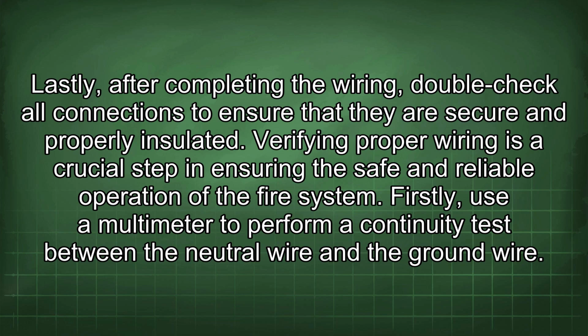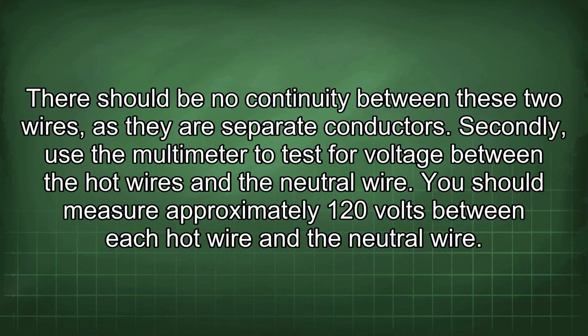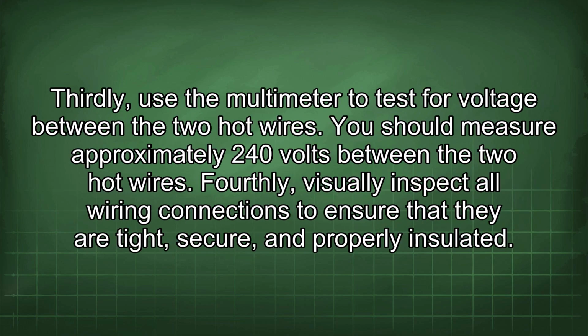Firstly, use a multimeter to perform a continuity test between the neutral wire and the ground wire. There should be no continuity between these two wires, as they are separate conductors. Secondly, use the multimeter to test for voltage between the hot wires and the neutral wire. You should measure approximately 120 volts between each hot wire and the neutral wire. Thirdly, use the multimeter to test for voltage between the two hot wires. You should measure approximately 240 volts between the two hot wires.